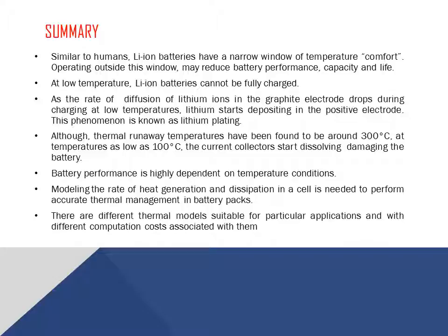Then, we found out that as the rate of diffusion of lithium ions in the graphite electrode drops during charging at low temperature, lithium starts depositing in the positive electrode. This phenomenon is known as lithium plating, and even though it occurs at low temperatures, it may end up causing thermal runaway.